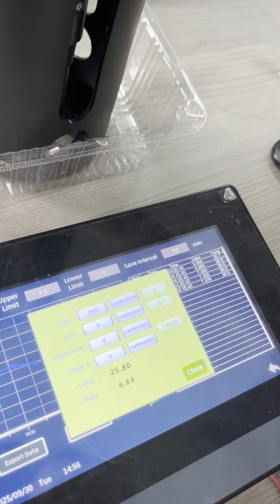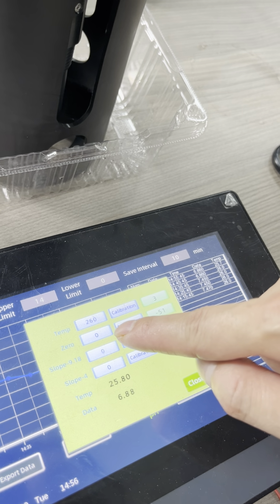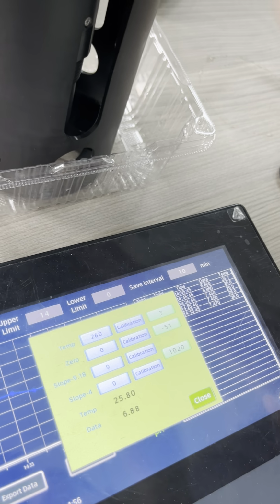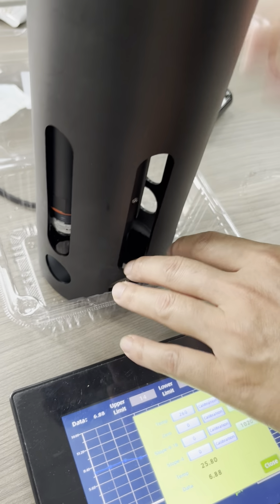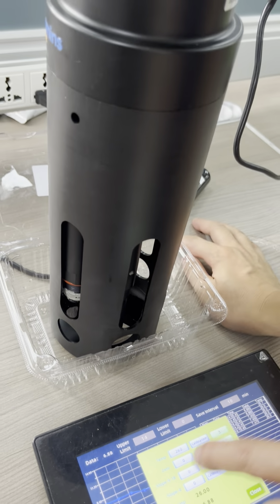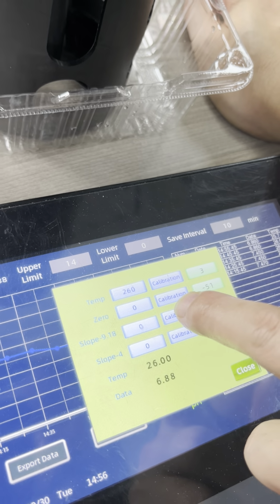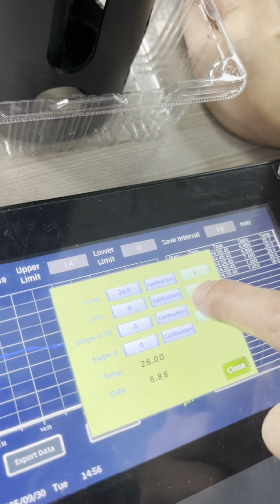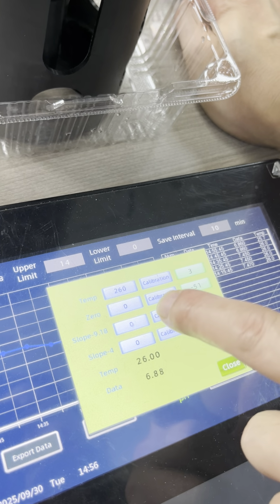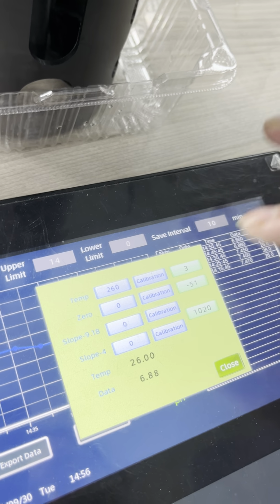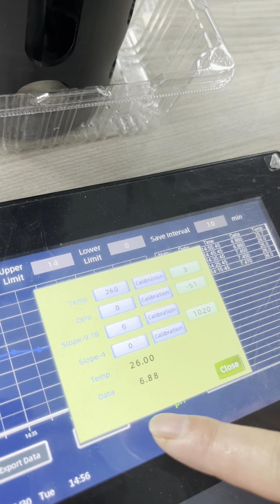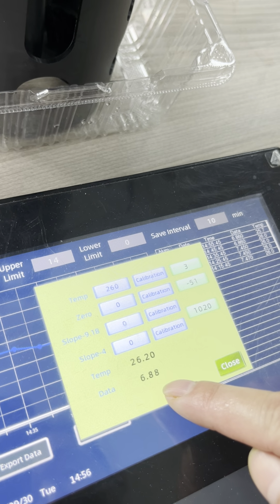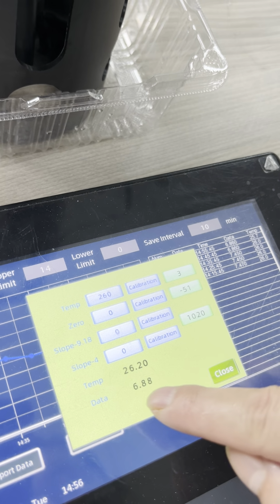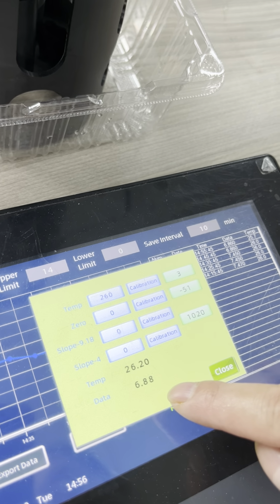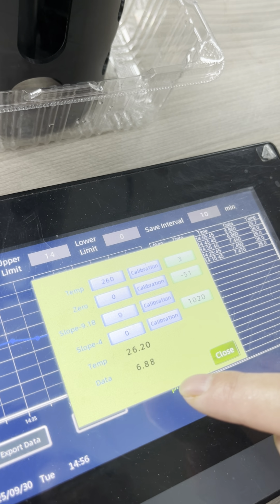Then we will do the zero calibration for the pH sensor. We put the sensor into the standard solution. The zero standard solution for the pH sensor is 6.86. When you check the data, after 3 minutes, the data will be stable. It will be around 6.86.